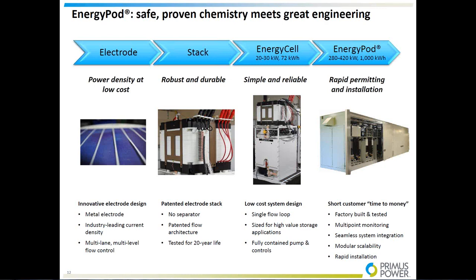Our solution is simply a megawatt-hour in a 40-foot shipping container. That megawatt-hour can be discharged anywhere from the tens of kilowatts up to 420 kilowatts on the DC side. We also have a single tank — unlike the typical two-tank standard for flow batteries, we have a single tank that we pump from different parts of to emulate a two-tank system, but with half the number of parts. That's one way we keep cost down and reliability high.